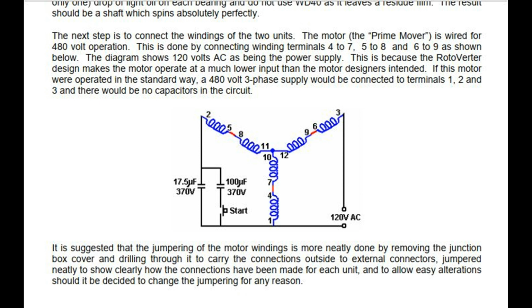The next step is to connect the windings of the two units. The motor, the prime mover, is wired for 480 volt operation. This is done by connecting winding terminals 4 to 7, 5 to 8 and 6 to 9 as shown below. The diagram shows 120 volts AC as being the power supply. This is because the rotoverter design makes the motor operate at a much lower input than the motor designers intended. If this motor were operated in the standard way, a 480 volt 3-phase supply would be connected to terminals 1, 2 and 3 and there would be no capacitors in the circuit.